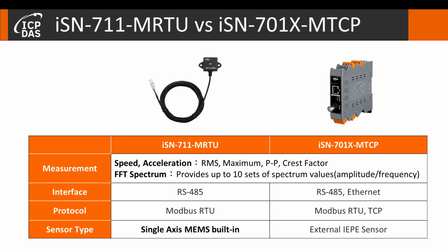The difference between the 2 modules is that ISN 711 MRTU is for RS485 and ISN 701X MTCP is for RS485 and Ethernet. In addition, ISN 711 MRTU has a single axis MEMS built-in sensor. However, ISN 701X MTCP needs to connect an external IEPE sensor.